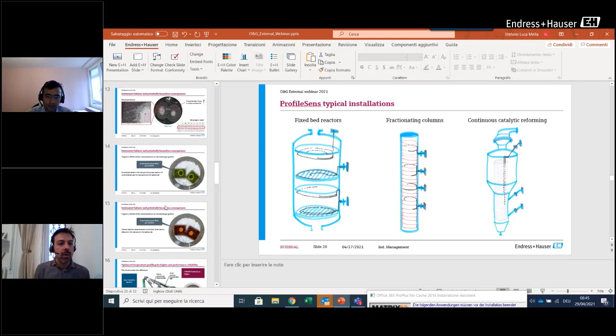With the standard sensors, we recommend not bending them in a way that the bending radius is lower than 5 times the diameter of the thermocouple. So if you have a thermocouple of 8 millimeters, the bending radius should not be less than 40 millimeters, which is already very, very tight. That's the minimum. During installation, as soon as it's possible, we do smoother bends anyway.